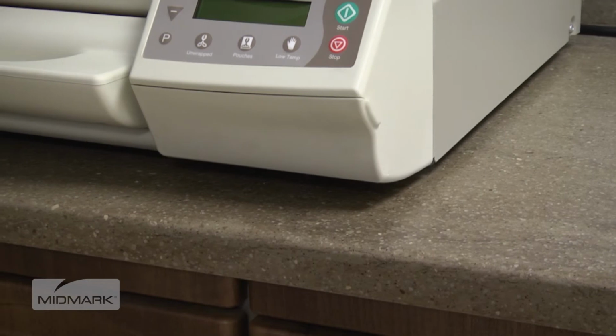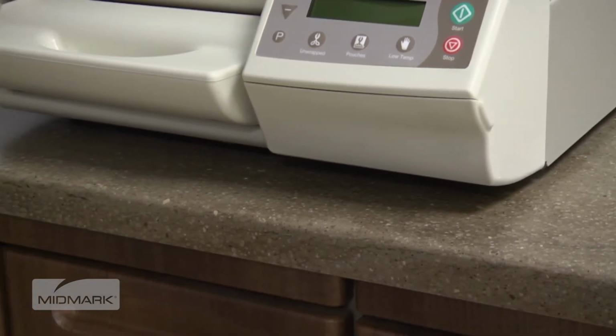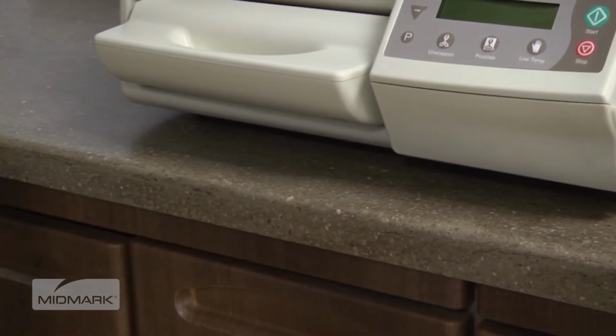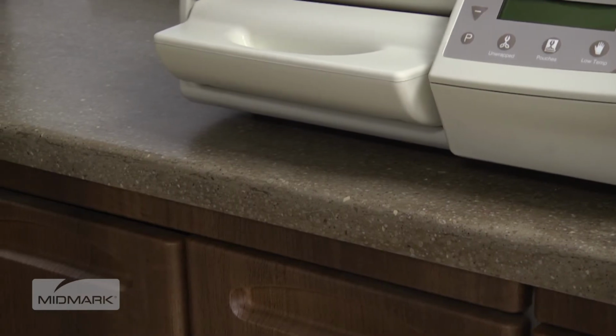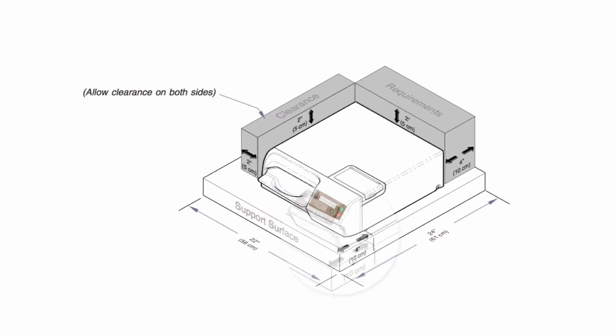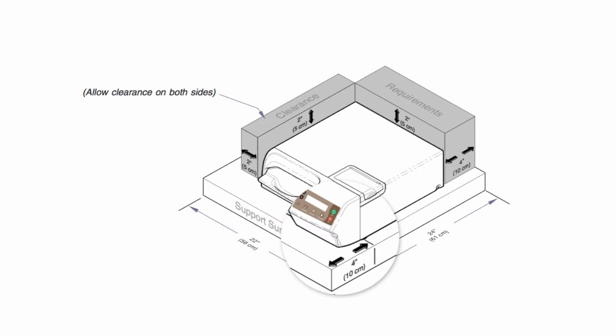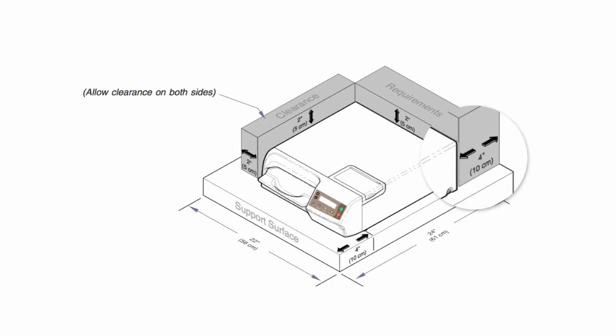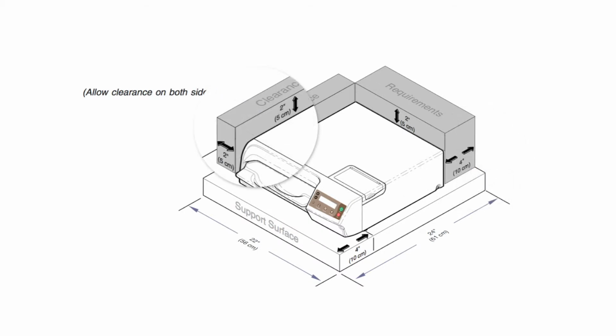Support surface materials should be water-resistant. For example, laminate, stainless steel, or stone. The surface must be level to ensure proper operation. Allow a 4-inch clearance from the front feet to the front of the support surface, 4 inches from the back of the unit to the back wall, and 2 inches on either side.